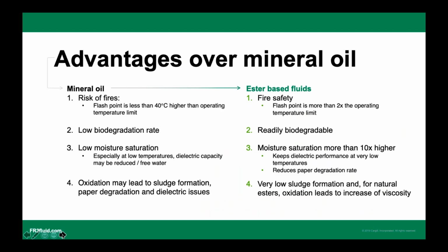Now, before I go to the product comparison, I would like to put up some comparison on the basic parameters of mineral oil and the esters in general. What we saw so far is about the risk of fire, the biodegradability, moisture issues with the conventional mineral oil design, and sludge formation in the transformer. So if you have ester inside, all these points can be overcome very easily. We'll discuss during the Q&A in detail. I'm sure people will have a lot of questions on that. Next slide, please.